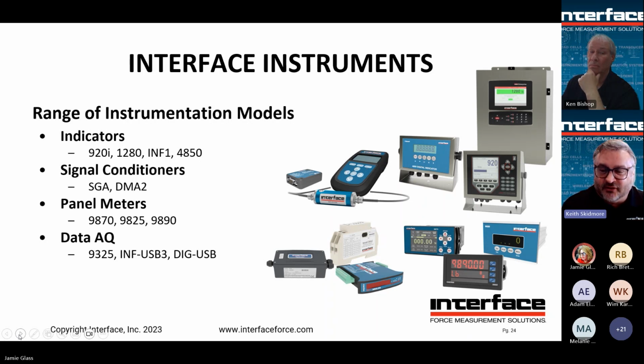Panel meters are displays, but they are not intended to stand alone. They can be mounted, say, inside a box or a panel. So say somebody had their own electrical panel, wanted to mount a display into it, the panel meter would work well. Panel meters display, they also may have alarm or digital functions and can be used to control other devices. And then, of course, data acquisition ranges from PLCs to standalone units that can log or control or take signals from multiple devices and log everything synchronously.